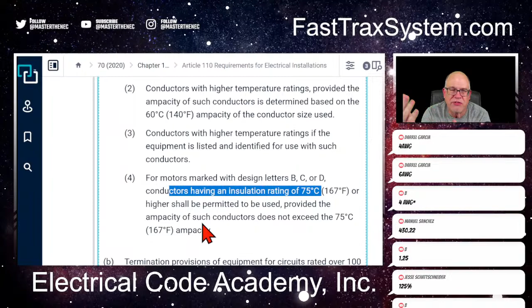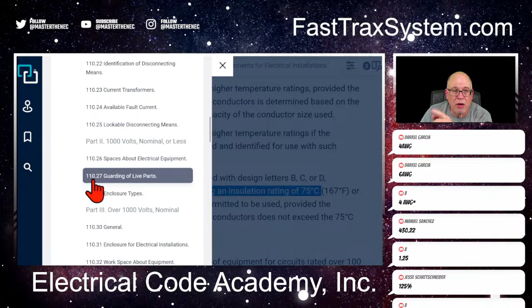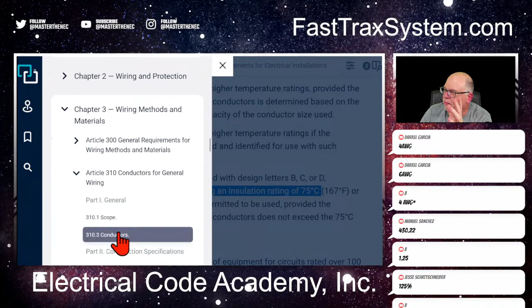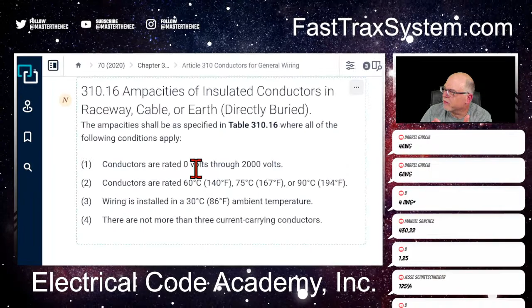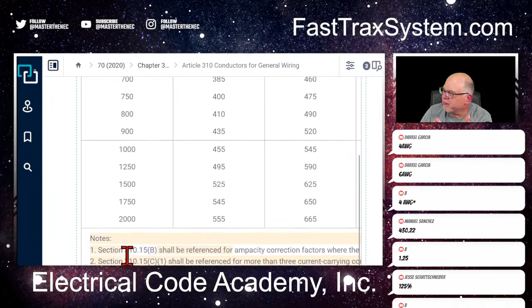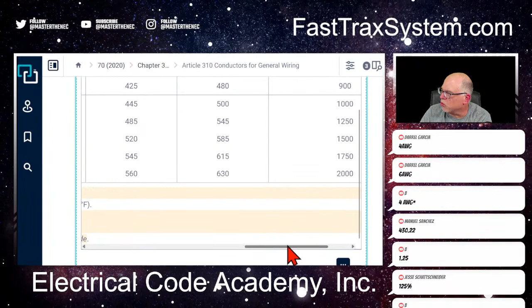Now remember, not all exams are going to be so logical, so make sure you check the other answers. Why is that important? I'm going to show you. I'm going to take you back to 310.16 to show you why it's important to be fully fluent when you're doing all this. We're back at the table. If I had said aluminum, go back over here to aluminum, and I want to get the 60 degree column just to show you. So this is the 75, and it was THW, but if we had followed 110.14(C) rules, then where we'd be over here, what do we need, 55 amps?